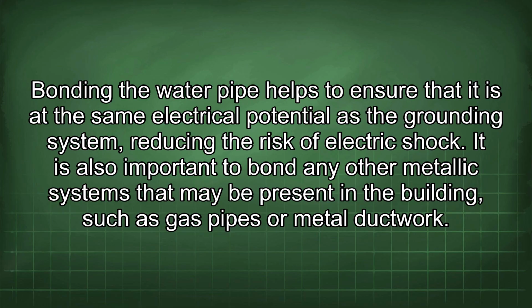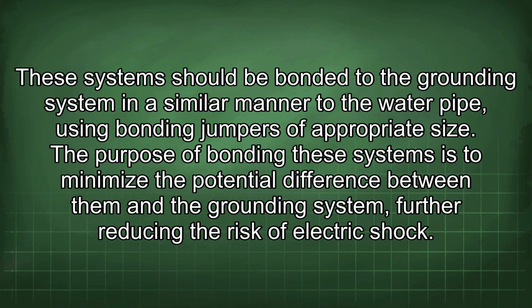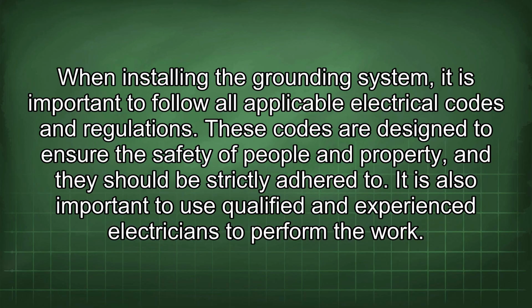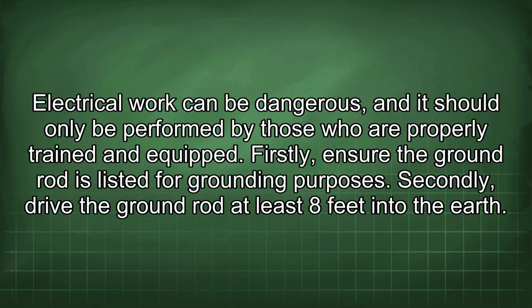It is also important to bond any other metallic systems that may be present in the building, such as gas pipes or metal ductwork. These systems should be bonded to the grounding system in a similar manner to the water pipe, using bonding jumpers of appropriate size. The purpose of bonding these systems is to minimize the potential difference between them and the grounding system, further reducing the risk of electric shock. When installing the grounding system, it is important to follow all applicable electrical codes and regulations. These codes are designed to ensure the safety of people and property, and they should be strictly adhered to. It is also important to use qualified and experienced electricians to perform the work. Electrical work can be dangerous, and it should only be performed by those who are properly trained and equipped.